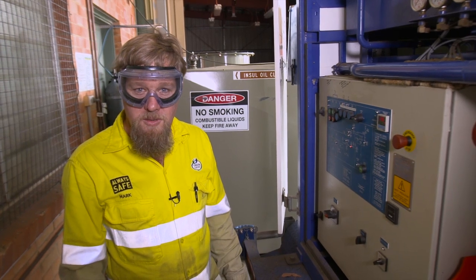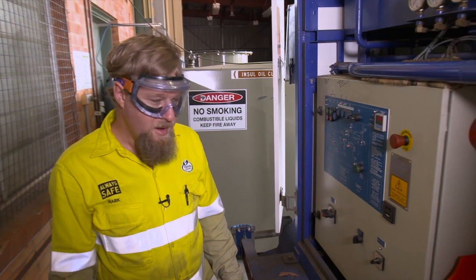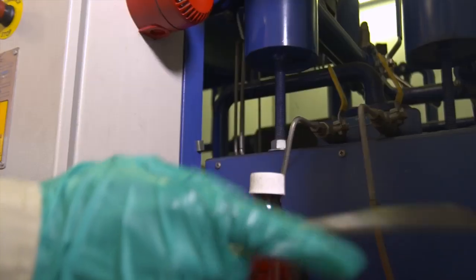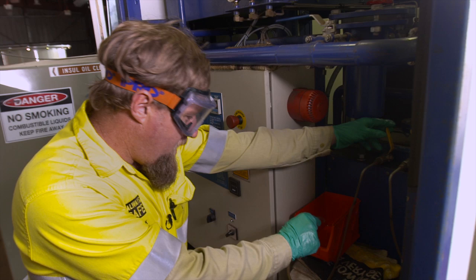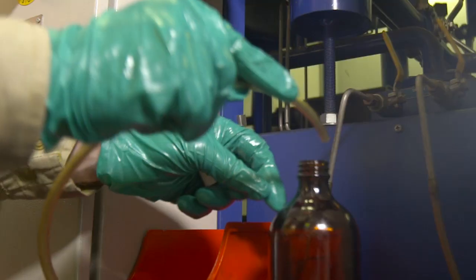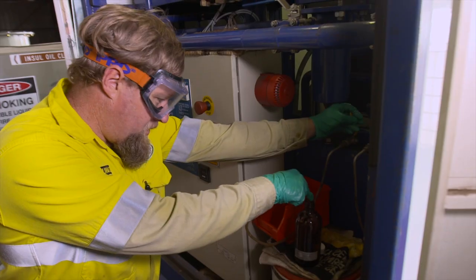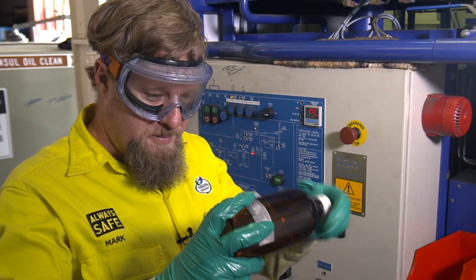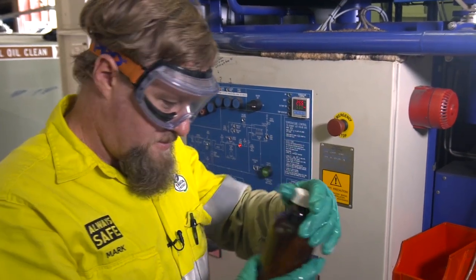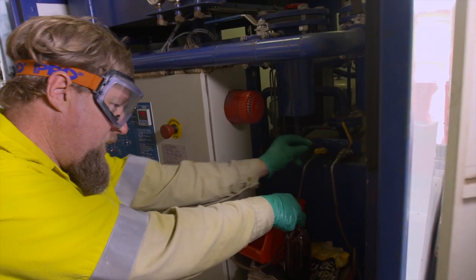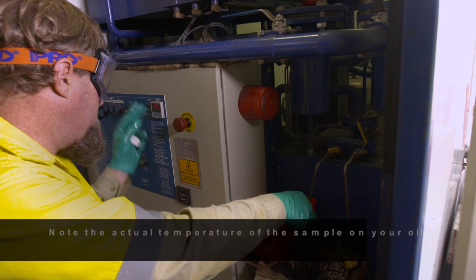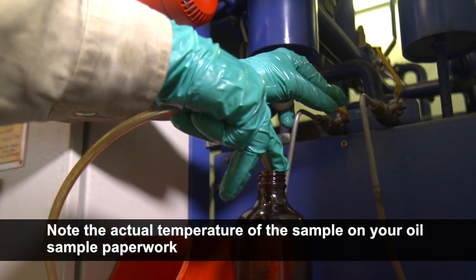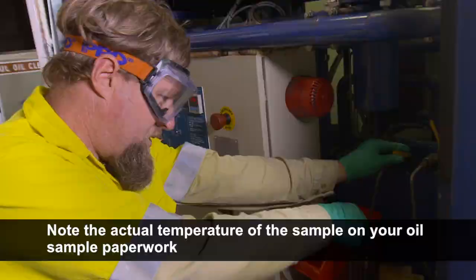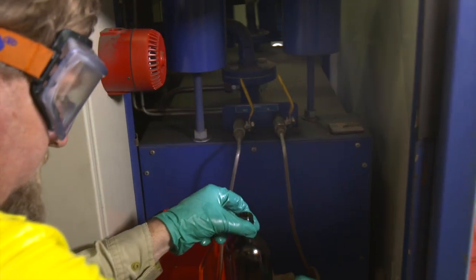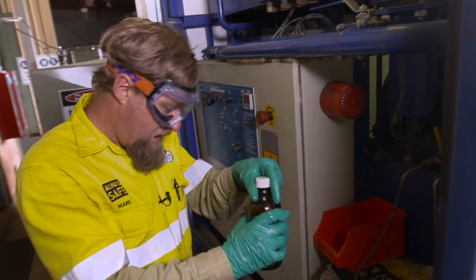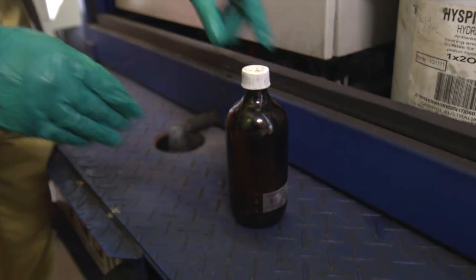When taking an oil sample from an oil treatment plant, this is how to do it. From the inlet side of your treatment plant, open the tap and disperse some oil, then flush your bottle, and then fill your bottle up. The oil coming out will be quite hot, about 55 degrees, which is what the treatment plant is set at. Once the sample has been taken, put the lid on and set the oil aside somewhere to cool down.